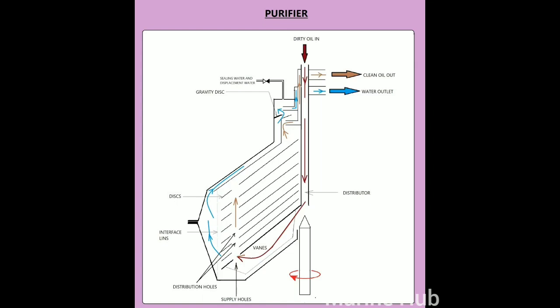Separation and clarification takes place between the discs. Water and sludge moving radially outwards pass along the undersurface of the discs, and the purified oil moving radially inwards passes over the upper surface of the discs. Water and light sludge particles are discharged at the water outlet. There is a sludge discharge cycle which will empty the bowl at designated intervals.